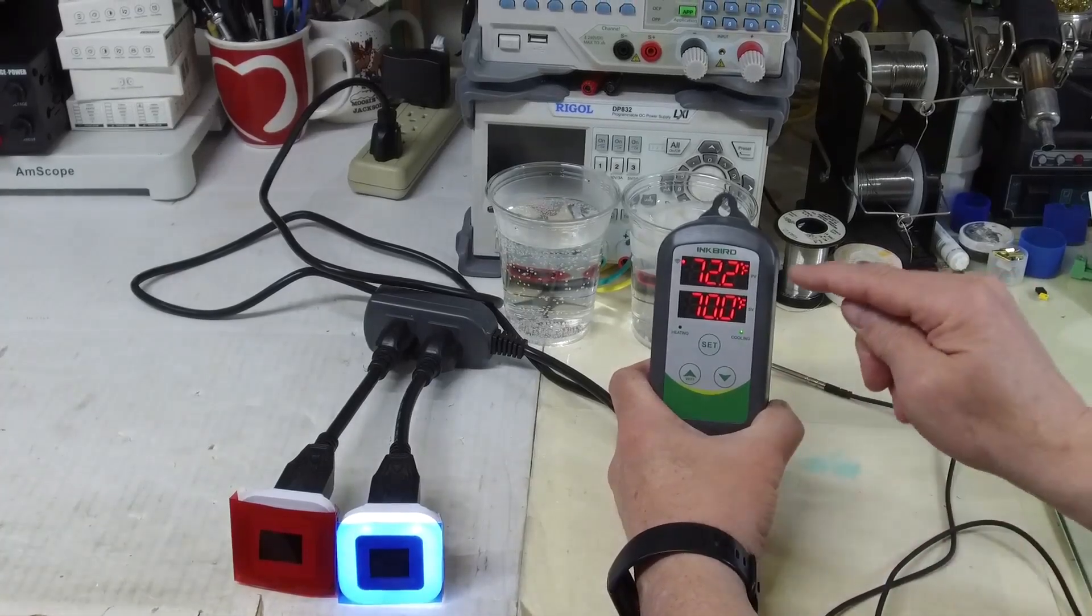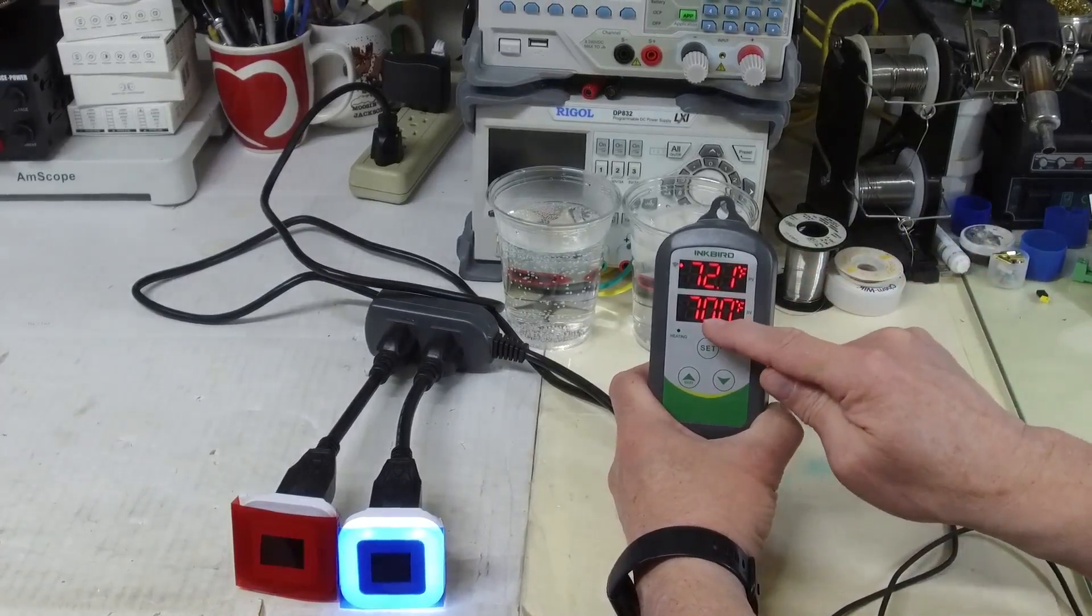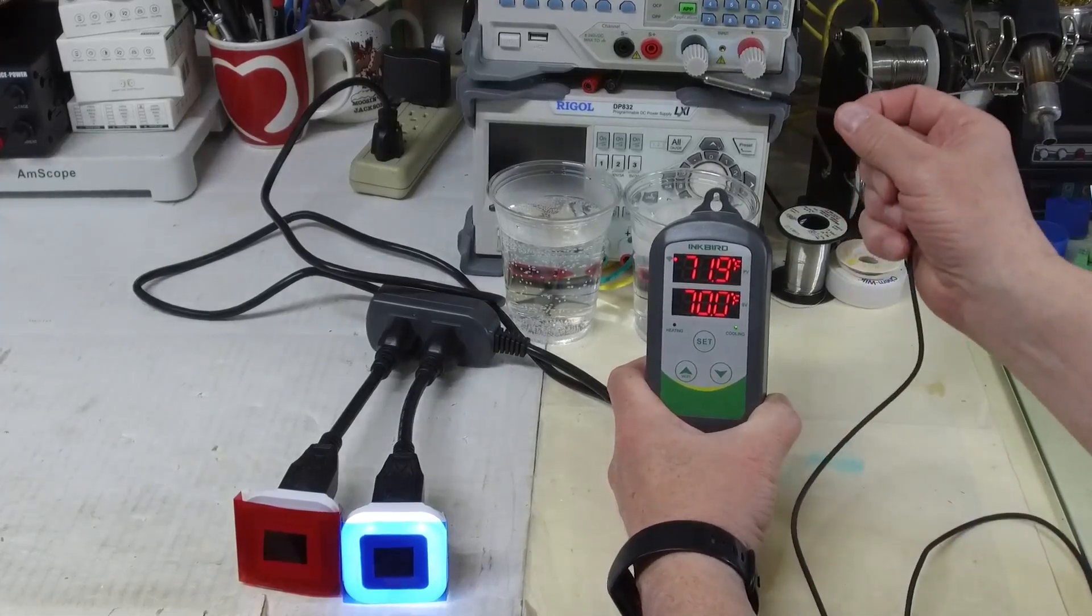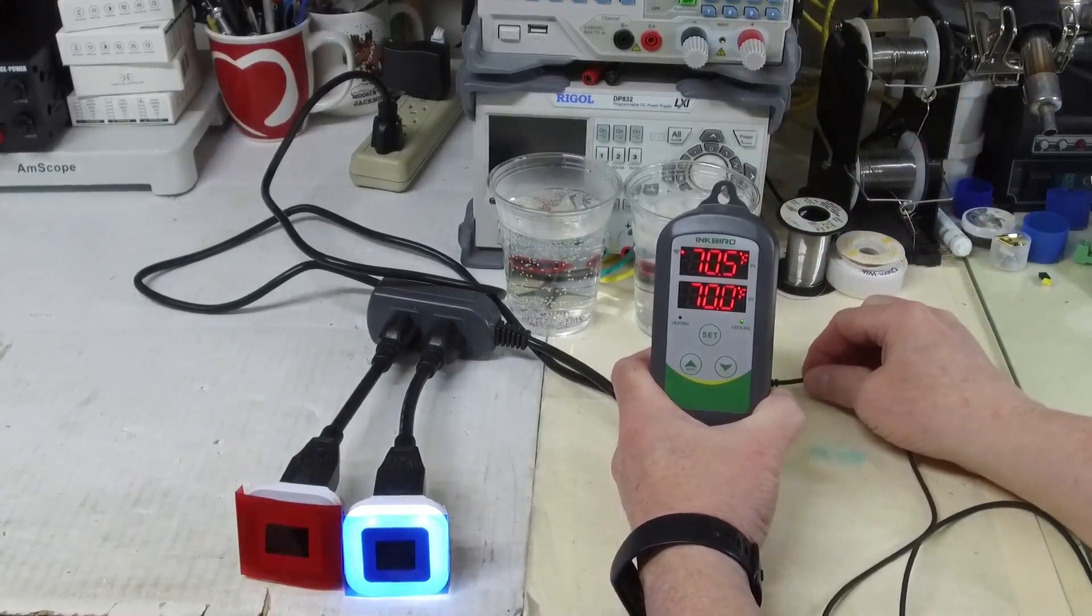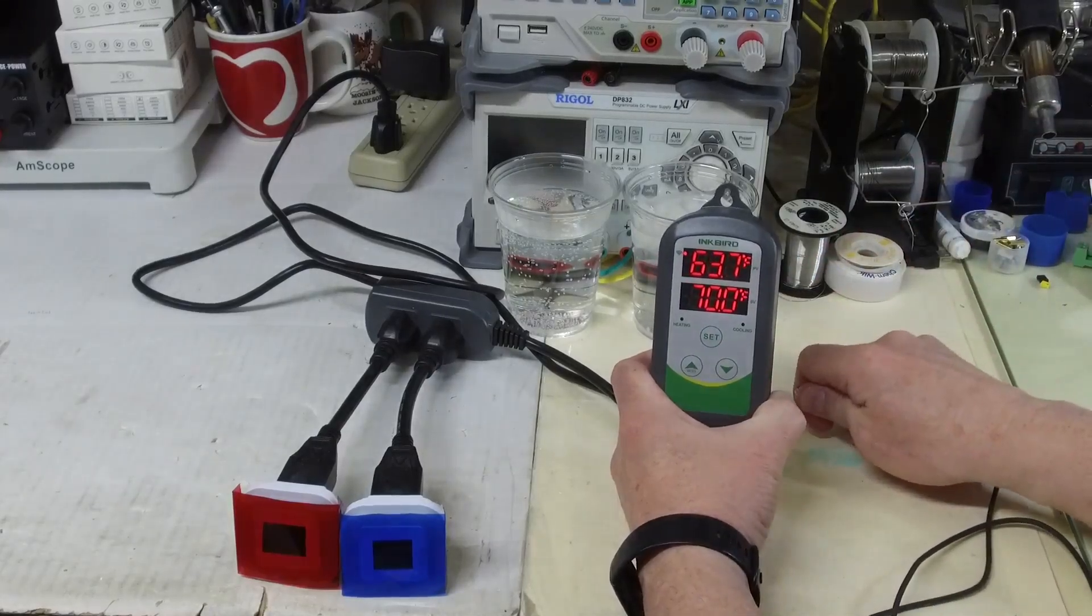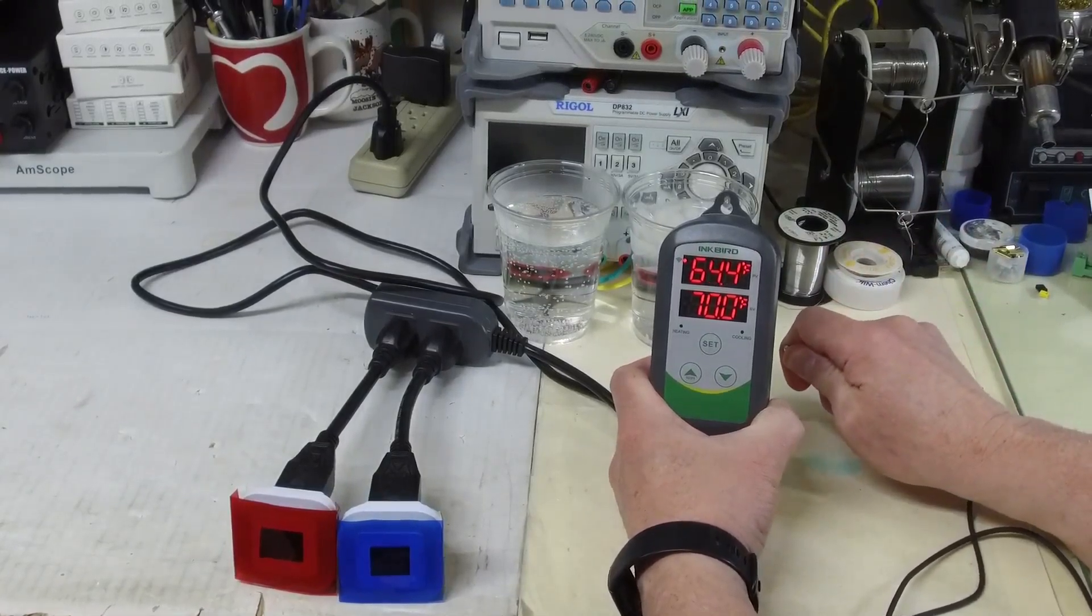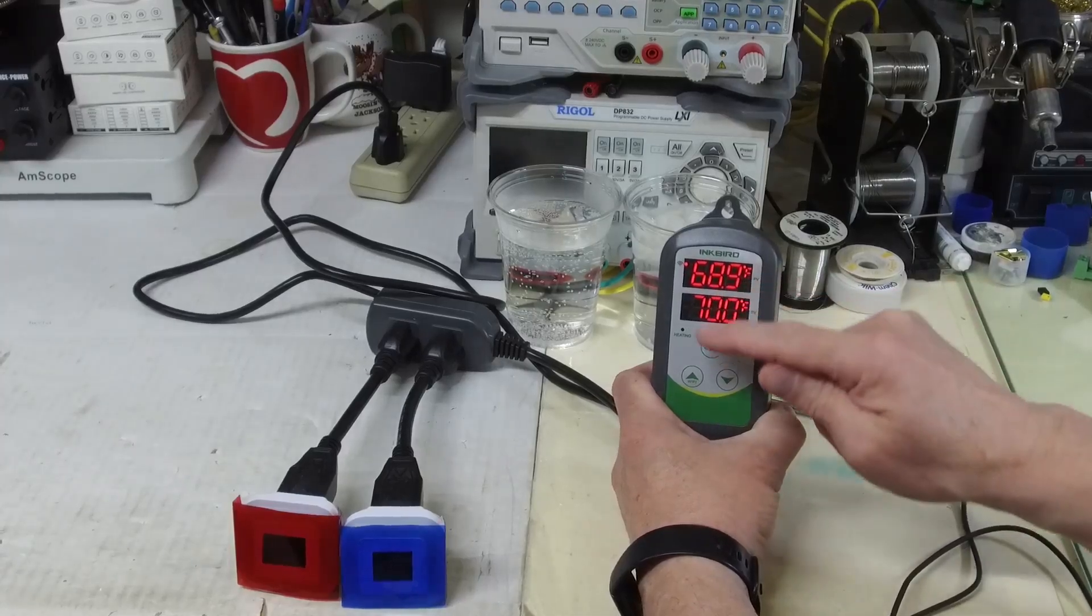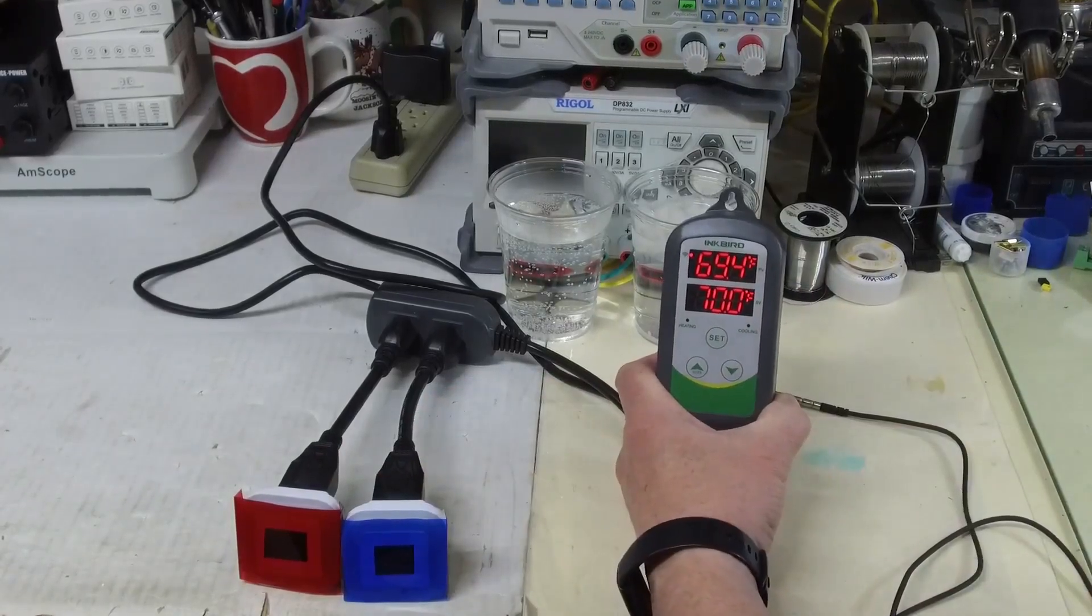It is initially going to try to cool down to this 70 degrees. I'm going to put this probe in some ice water just to help it get there real fast. Okay, it turned off and I'm going to apply some heat with my fingers here to try to keep this in that 10 degree window. As long as we now stay between 80 degrees and 60 degrees, our cooling and heating will not energize.